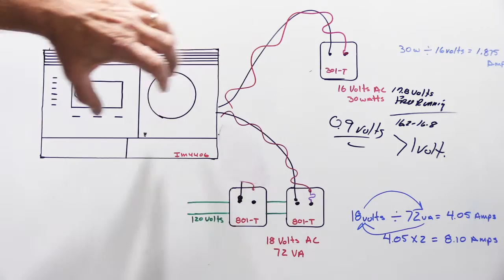It wants more power than it can supply, and what happens is the master station drags the voltage down to near zero. And the byproduct of the transformer being dragged down to near zero and being overloaded is that it's going to start to get hot. And it's going to get hot pretty quickly. You can go from nominal room temperature to too hot to hold your hand on it in a matter of just a couple of minutes.